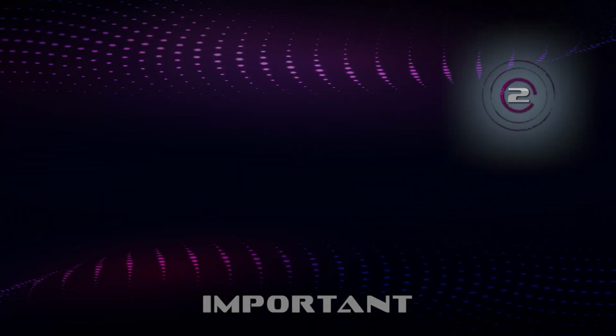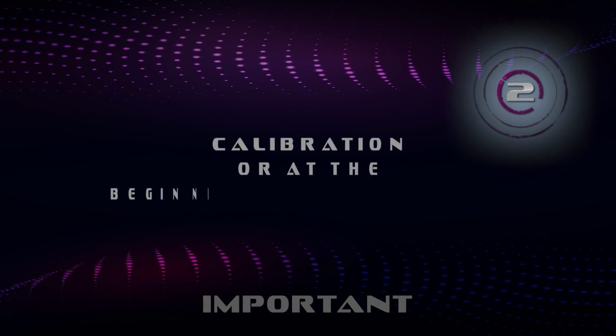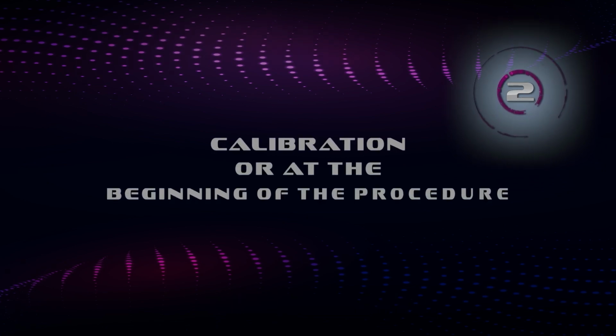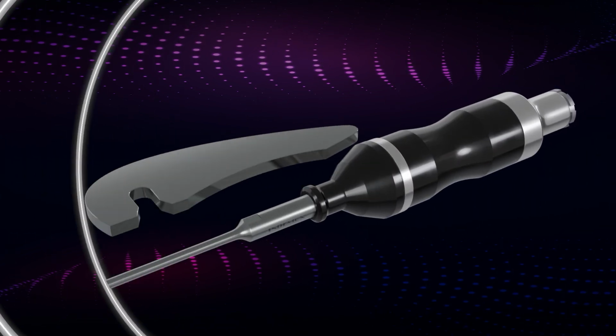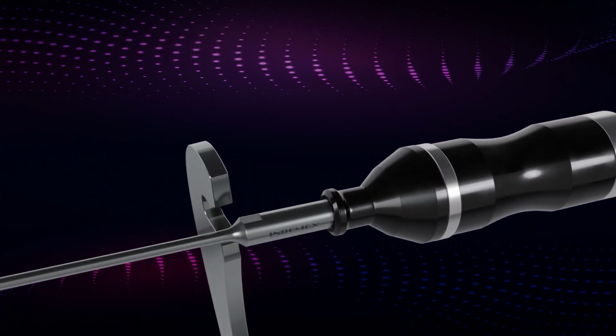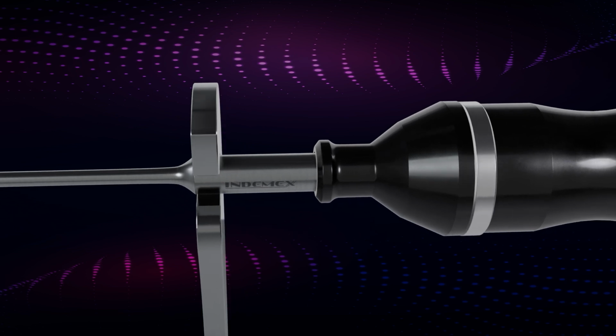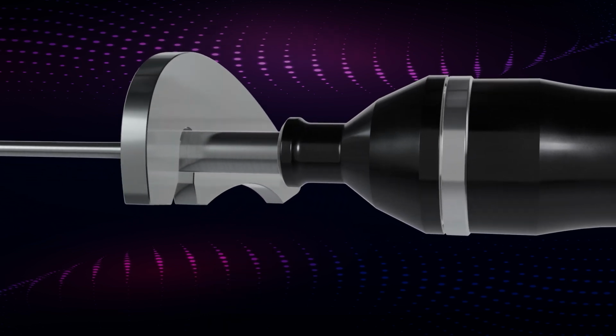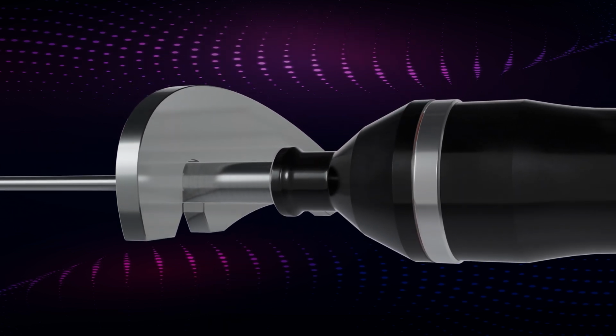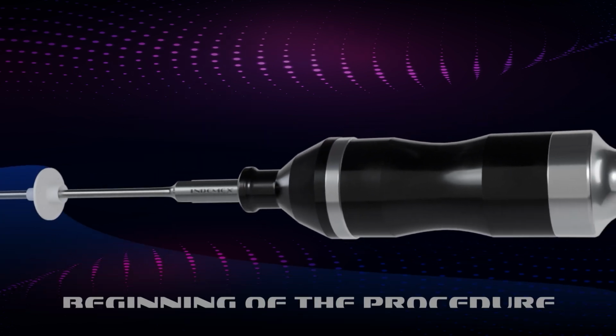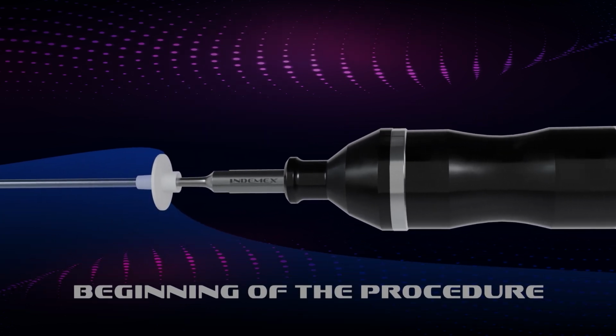2. If you notice that during calibration or at the beginning of the procedure, the handpiece produces a resonant sound, you should stop pressing the pedal and apply more force to tighten the sonotrode and adjust it more firmly to the handpiece. It is recommended that the handpiece be already inside to start the procedure.